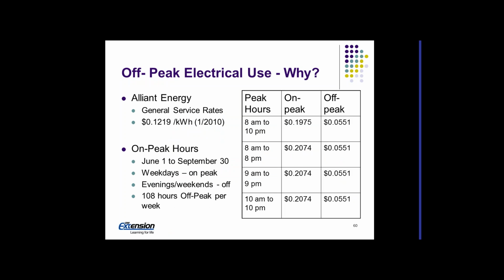Off-peak electric is another thing we can do to save energy. It doesn't reduce energy usage, but it saves energy costs. So here's an example. Their general service rate is 12 cents a kilowatt hour. This was in 2010. Their off-peak rate, depending on the hours, so this is a 14-hour period, this is a 12-hour period, was about 20 to 21 cents on peak and about 5.5 cents off peak. So the more you can shift to off peak, the lower your cost is.